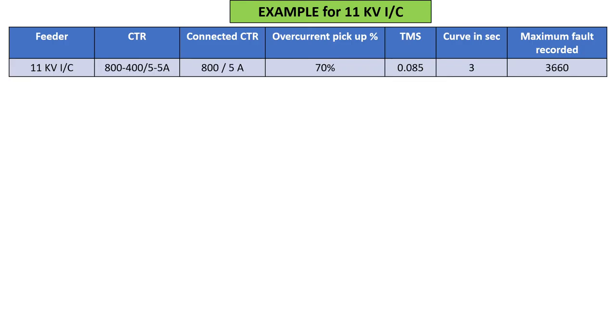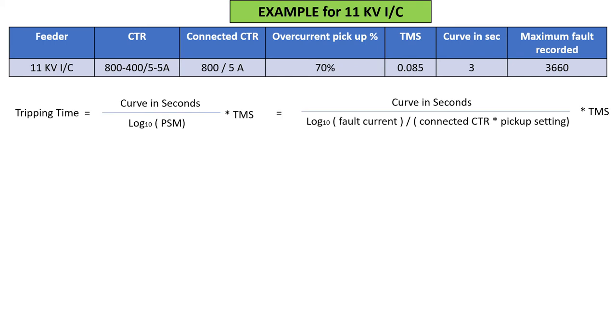Taking the example of 11 kV incomer, these are the available details that we need to set: CTR, connected CTR (we selected 800/5 A), pickup percentage set in the relay at 70%, TMS at 0.085, curve, and fault current recorded at 3660 A. Now let's find the pickup current. Multiply CTR 800 ampere with pickup percentage 0.7, so our pickup is 560 ampere.